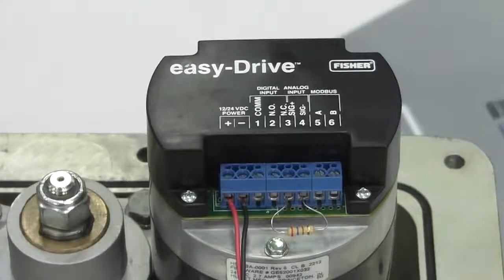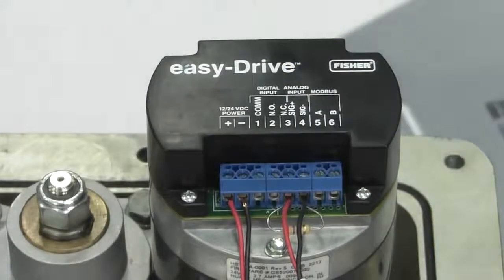When looking at the analog input terminals, you should notice a 250 ohm resistor installed between terminals 3 and 4. This should be standard for all positioning units leaving the factory. If you do not see a 250 ohm resistor installed, please install the resistor before connecting the signal to the actuator. Analog signal wiring should be installed across terminals 3 and 4 along with the 250 ohm resistor, connecting the positive and negative signal wires respectively.